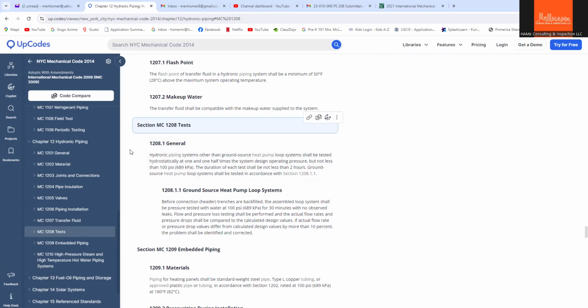So this is under the mechanical chapter 1208.1, the general. Hydronic piping systems, other than ground source heat pump loop systems, shall be tested hydrostatically, meaning with water, at 1.5 times the system design operating pressure, but not less than 100 psi. And the duration of the test shall not be less than 2 hours. So I believe the system that we're testing is more than 100, that's why we are testing it to 240 psi. It should not be lower.